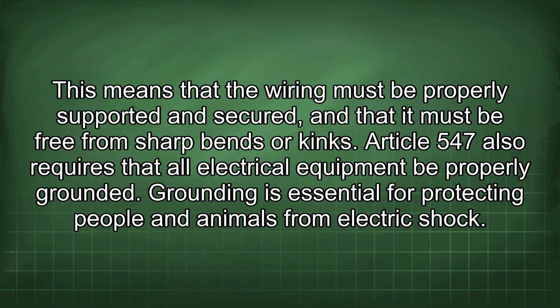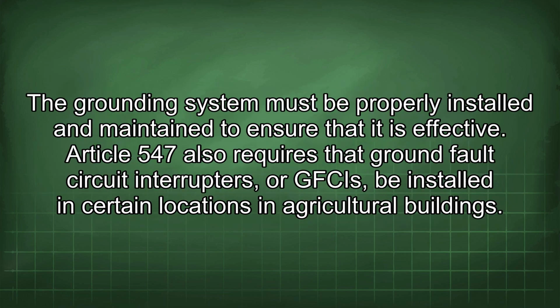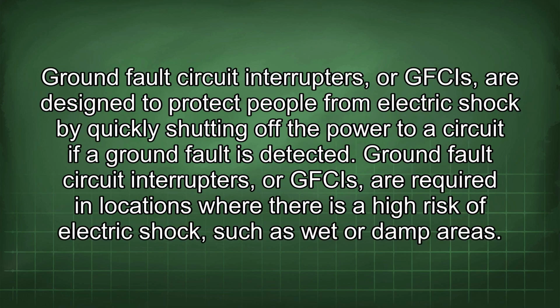Grounding is essential for protecting people and animals from electric shock. The grounding system must be properly installed and maintained to ensure that it is effective. Article 547 also requires that ground fault circuit interrupters, or GFCIs, be installed in certain locations in agricultural buildings. GFCIs are designed to protect people from electric shock by quickly shutting off the power to a circuit if a ground fault is detected.